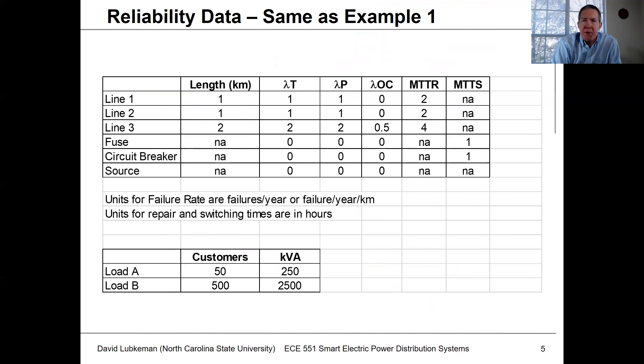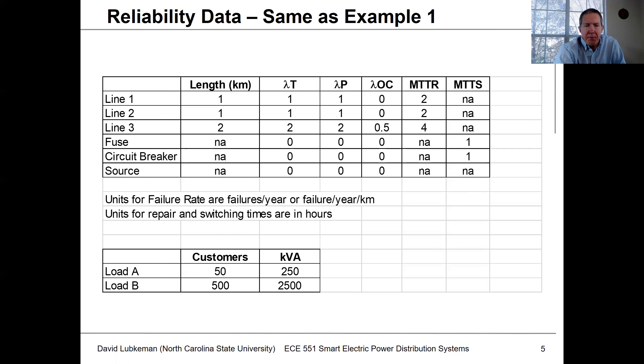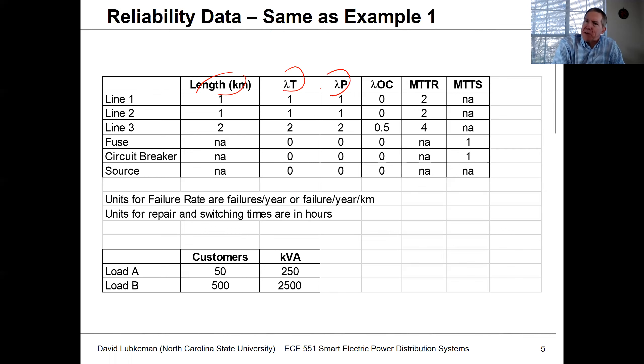The reliability data for this first example will be the same as in the part one presentation. For each segment, I've got a length, a temporary failure rate, and a permanent failure rate. In a more realistic dataset, you would expect two to three times more temporary faults than permanent faults, but it depends on the situation.